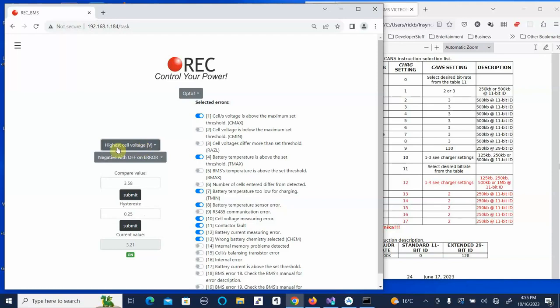So let's say we want to trigger an alarm when the highest cell voltage exceeds a certain point. Okay, so we would go highest cell voltage would be off with an error or on with an error. We would set it if it goes above, let's say, 3.7 volts, and with a quarter volt hysteresis. We can also include selected errors. So if any one of these errors is triggered, it will also trigger that alarm. And that's all there is to it.